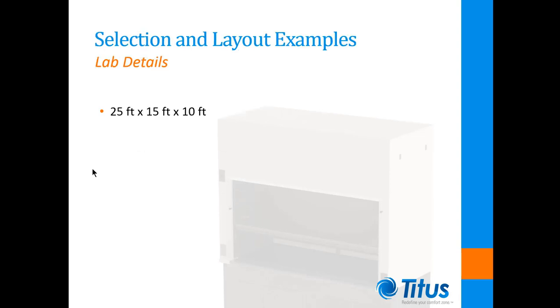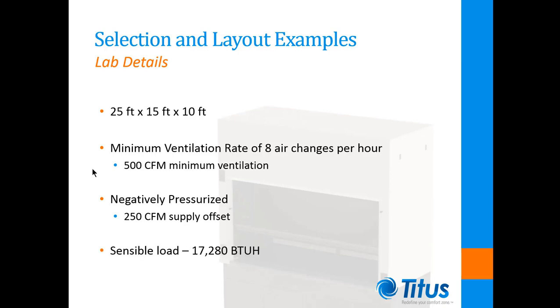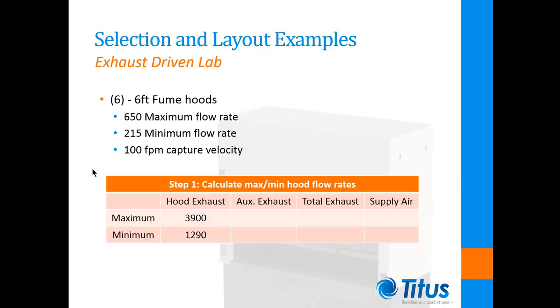Now we'll take a look at a few examples. For these examples we will consider a 25 foot by 15 foot lab with a 10 foot ceiling. The minimum ventilation rate will be 8 air changes per hour, which is 500 CFM based on the room volume. To maintain negative pressurization we will maintain a supply airflow rate of 250 CFM less than the exhaust flow rate. The sensible load in these labs is 17,280 BTU per hour. The fume hoods used will be 6-foot hoods with maximum exhaust flow rates of 650 CFM each, minimum airflow rates of 215 CFM, and a capture velocity of 100 feet per minute.